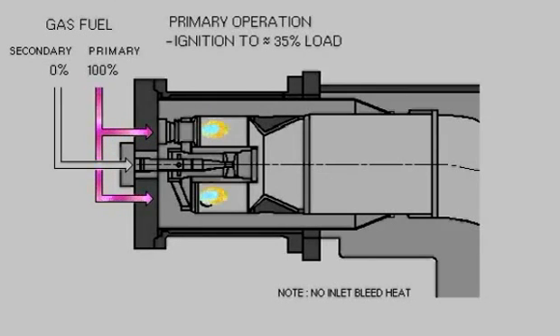Primary mode: fuel is supplied to the primary nozzles only and flame is in the primary stage only. This mode of operation is used to ignite, accelerate and operate the machine over low to mid loads up to a pre-selected combustion reference temperature.